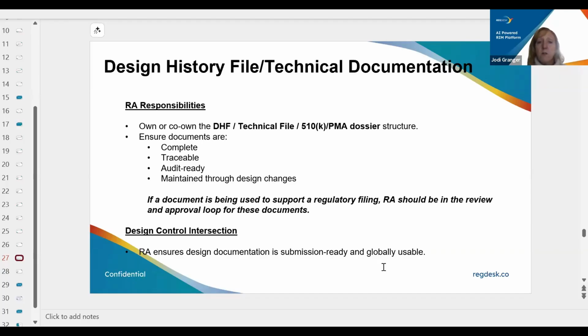So it's best if you ensure regulatory is in the process for reviewing those on the front end. You don't want to have to go back after you've done a shelf life study, as an example, and you've waited months to collect that data to find that the protocol was lacking in some way, and you now don't have adequate data that will satisfy a regulatory authority.